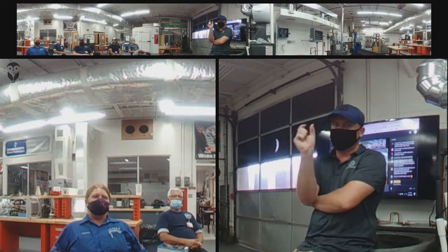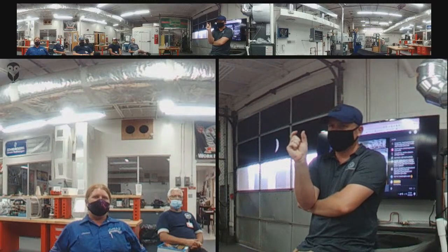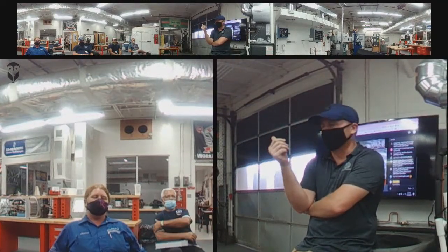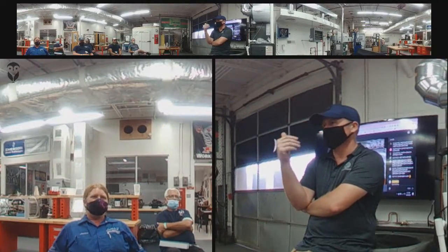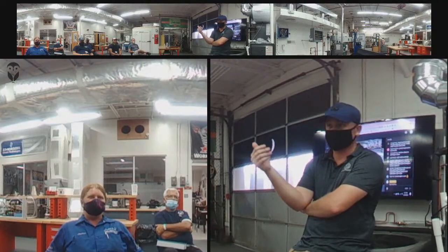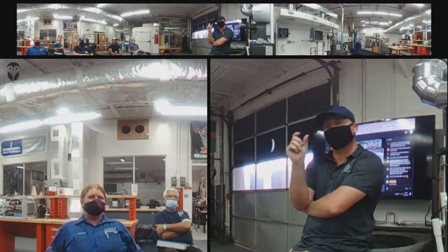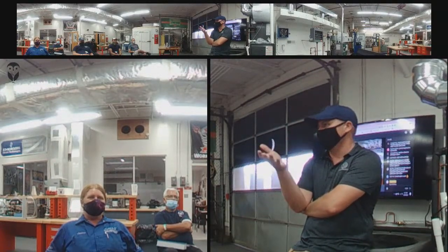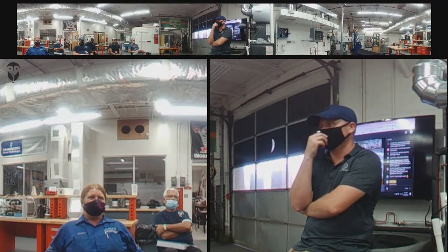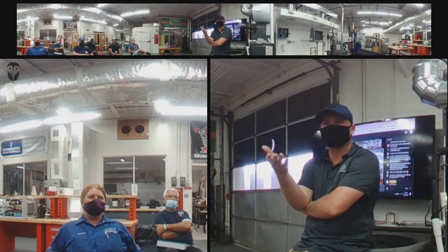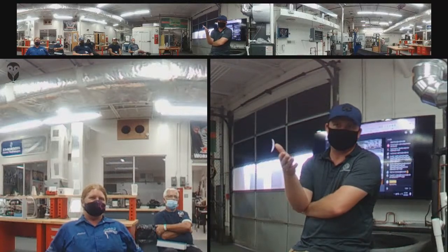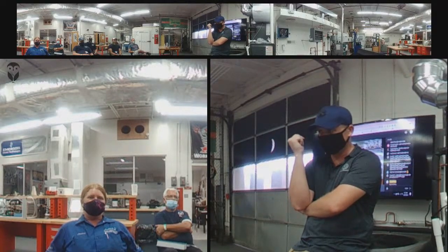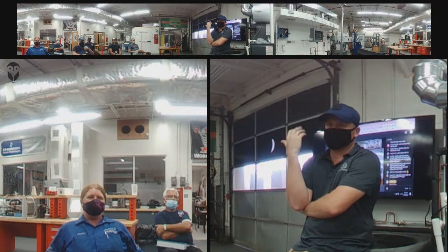It's important to get the entire joint hot enough that the solder, or alloy, is the right way of saying it, pulls into that joint. It's also helpful to use better quality alloys, because those flow better and are more ductile, so they don't crack as easily. But often it's just not getting it hot enough. Whoever's doing the brazing is afraid of burning up a valve. They're afraid of doing the wrong thing, and that's good. But often it's just a matter of not getting it hot enough.